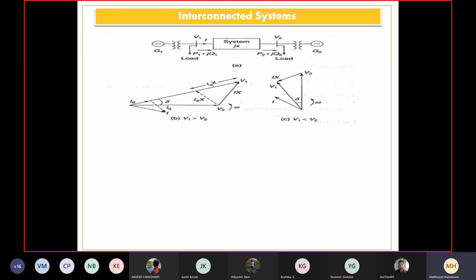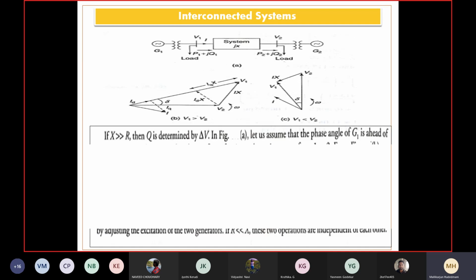Similarly, we have interconnected systems. When we have two systems interconnected, how does reactive power come into the picture and play its role? You can see two systems interconnected. One system has a generator and transformer at bus 1 and a load. The other system has generator 2 and transformer at bus 2, connected by a line impedance or reactance jX, which you can see in the representation. Terminal voltages of the buses are respectively V1, V2. Power flowing from 1 to 2 and on the other side is marked on the system as P1 + jQ1, P2 + jQ2. From this perspective, let's see what happens.